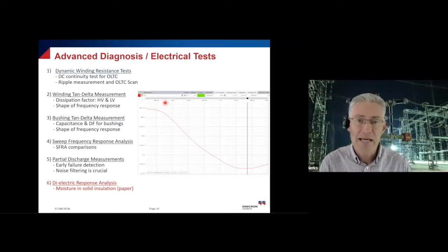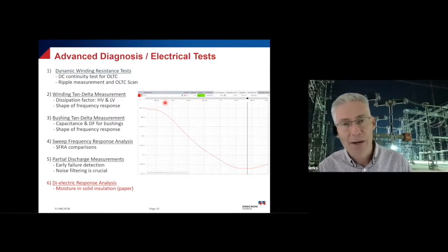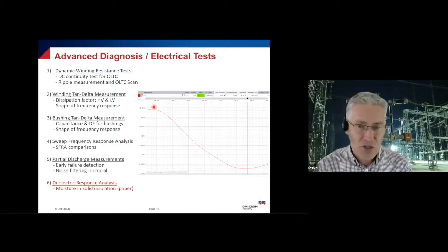It is basically a tan delta measurement over a very large frequency range, typically in the region of 0.1 millihertz all the way up to 1 kilohertz. And from the shape of this curve, we can then determine, by using certain modeling techniques, what the actual moisture is inside the transformer.